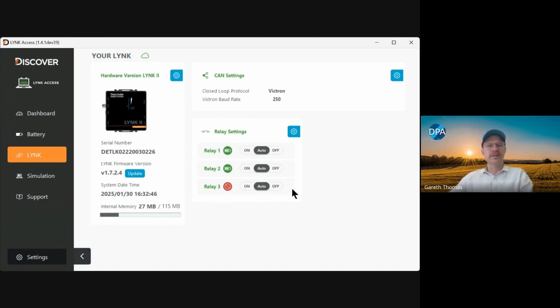So what we've got here is LYNK Access, a program you download from Discover and load onto your PC. You plug a USB cable from the LYNK II into your PC, and then you can see what's happening with this BMS. This is connected via a Cat5 cable to the top battery of the stack, and the rest are daisy chained down from there.